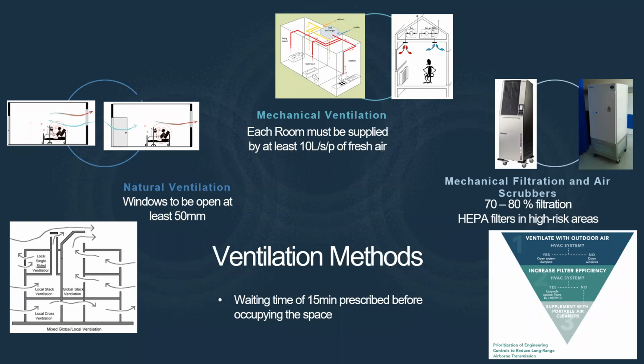The mechanical ventilation is a little bit more intricate and a little bit more complex, because now you need to force a certain amount of fresh air into a particular space. And it's typically gauged against a quantification of people in a particular room. And the requirement that's spelled out in the Department of Health guideline for COVID control in the HVAC environment is 10 liters per second per patient. So if you have, let's say, 4 patients in a room, you will typically need 40 liters a second to satisfy the requirement with regards to fresh air discharge into the room.